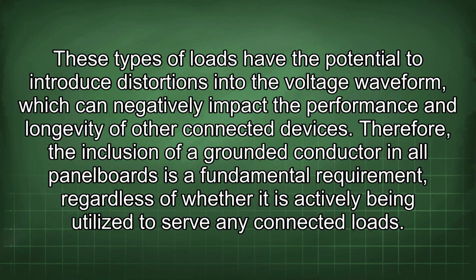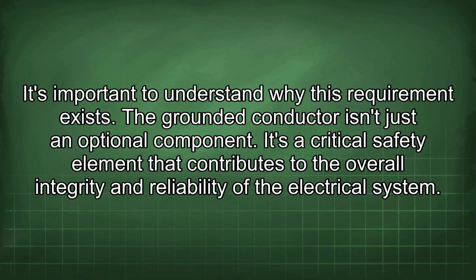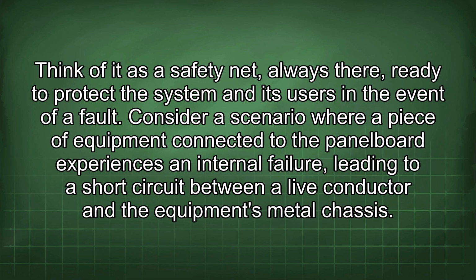Therefore, the inclusion of a grounded conductor in all panel boards is a fundamental requirement, regardless of whether it is actively being utilized to serve any connected loads. It's important to understand why this requirement exists. The grounded conductor isn't just an optional component. It's a critical safety element that contributes to the overall integrity and reliability of the electrical system. Think of it as a safety net, always there, ready to protect the system and its users in the event of a fault.